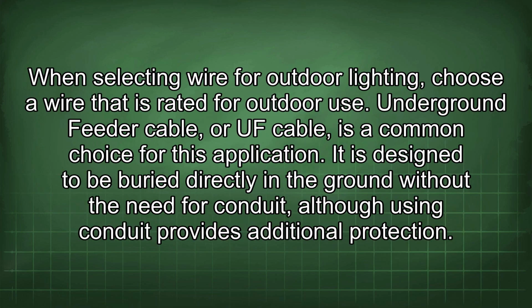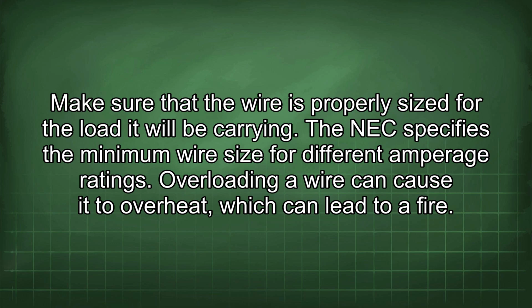When selecting wire for outdoor lighting, choose a wire that is rated for outdoor use. Underground feeder cable, or UF cable, is a common choice for this application. It is designed to be buried directly in the ground without the need for conduit, although using conduit provides additional protection. Make sure that the wire is properly sized for the load it will be carrying. The NEC specifies the minimum wire size for different amperage ratings. Overloading a wire can cause it to overheat, which can lead to a fire.